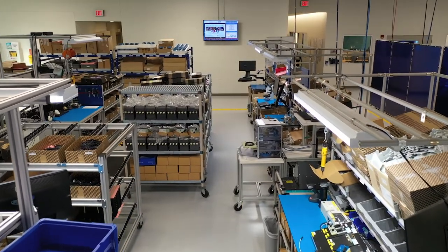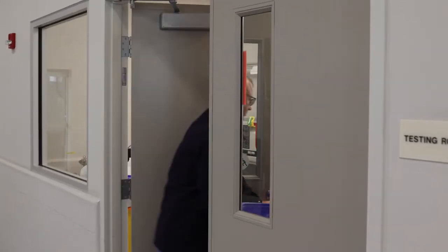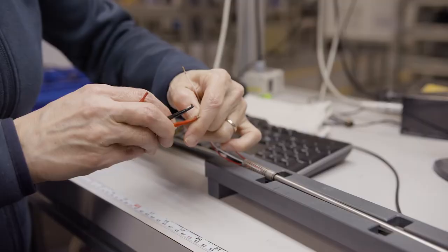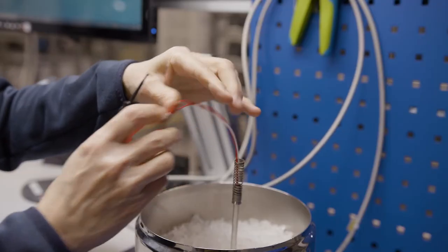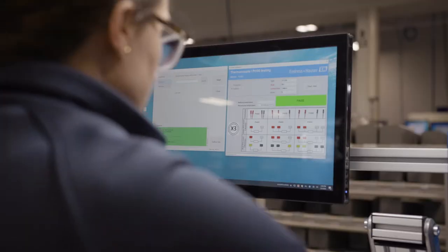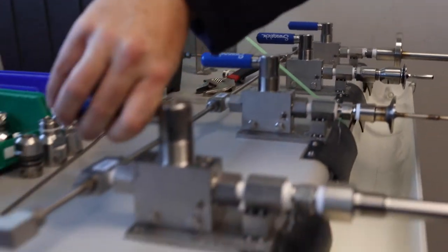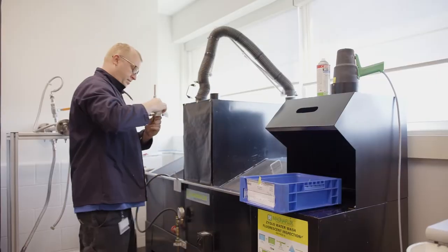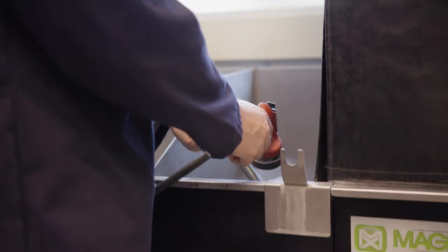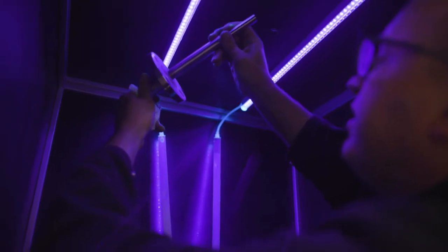All our temperature measuring devices endure rigorous testing to ensure the quality of our products. Each temperature sensor we fabricate goes through a high voltage insulation test and ice bath comparison to ensure performance and stated accuracies are met. Our non-destructive testing options for thermowells include internal and external hydrostatic pressure testing, dye penetrant testing, and surface roughness. Other tests include positive material identification and X-ray.